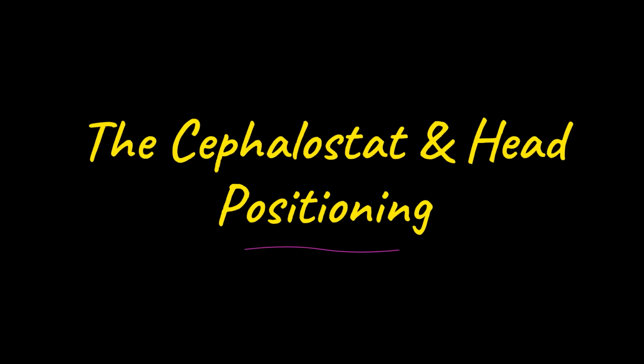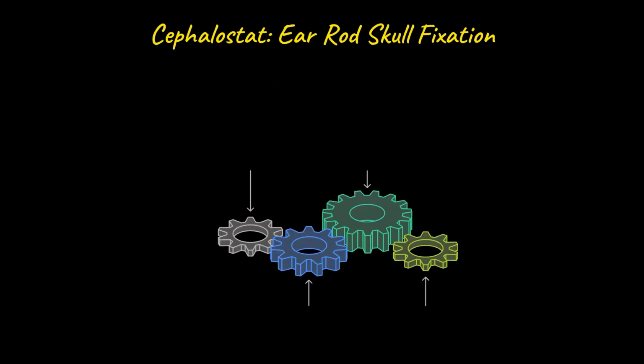The cephalostat is the device behind cephalometric imaging, a skull profile X-ray used to track jaw and tooth movement across orthodontic treatment. Understanding why it exists means understanding why reproducibility matters so much in this kind of imaging. The ear rods seat inside the external ear canals on both sides of the head, locking the skull at two fixed bony landmarks. A nasal support then orients the face to a standard reference plane, so the source to patient and patient to receptor relationships stay identical from one visit to the next.